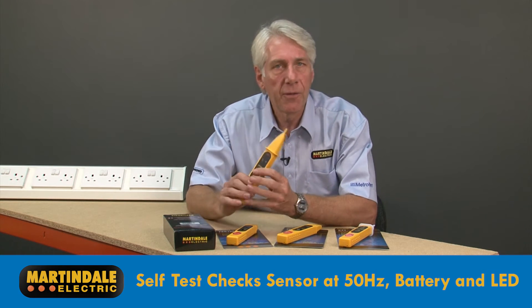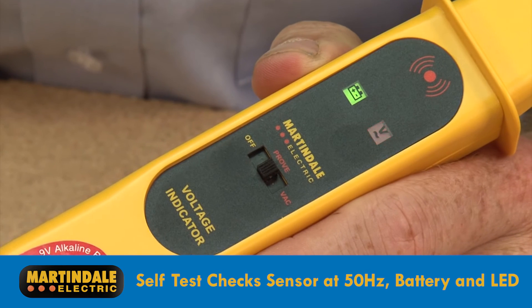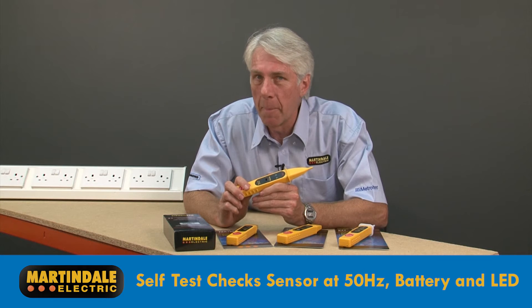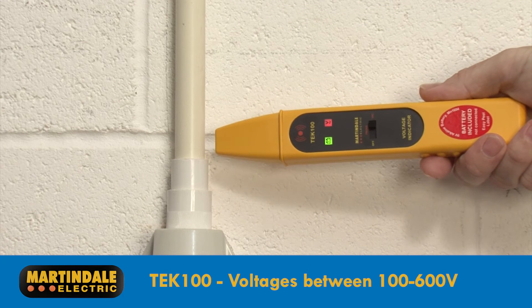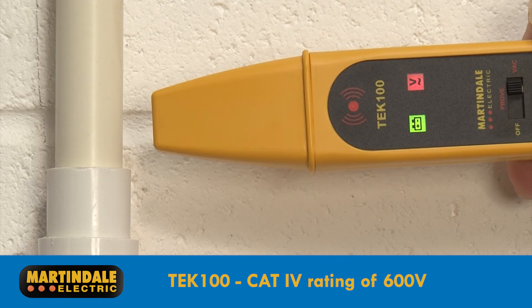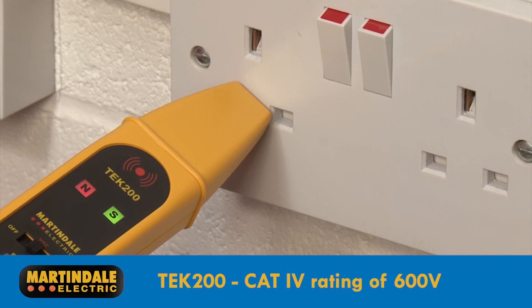The built-in self-test of the TEK series checks the sensor at 50Hz, the battery and LED — a great solution ensuring reliable results every time. The TEK100 will detect the presence of voltages ranging between 100 and 600 volts and is CAT4 safety rated to 600 volts. The TEK200 is also rated between 100 and 600 volts with a CAT4 rating of 600 volts.